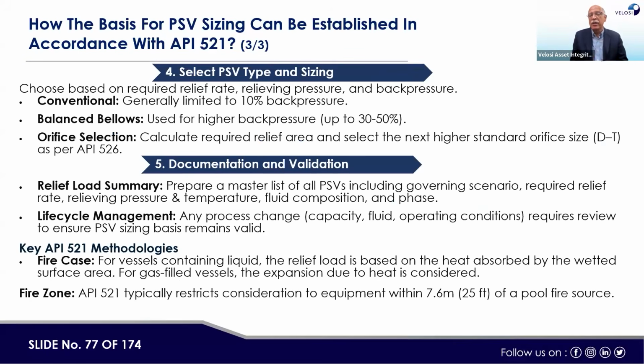Normally the average PSV lifting scenario, or time between PSV liftings, is 5 to 10 years, one time. This is normal. Then we have to select the PSV type, whether conventional type, balanced bellow type, then orifice selection and the size of the PSV also. Then whatever process we are following, as per API 520 and 521, complete documentation is required to be selected and registered.